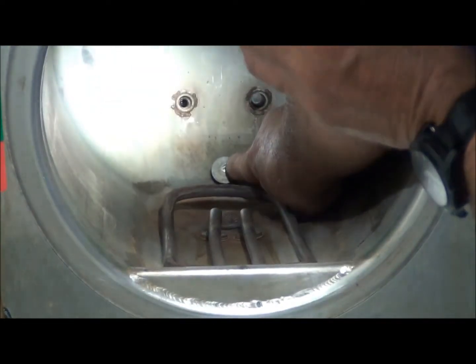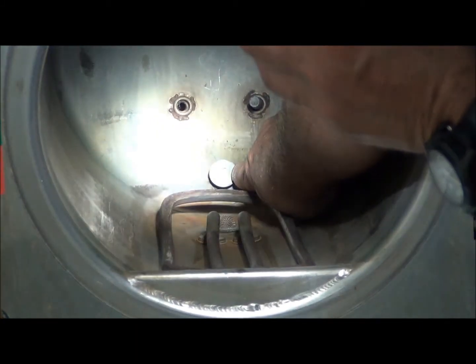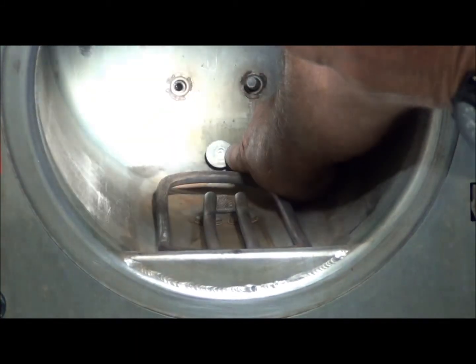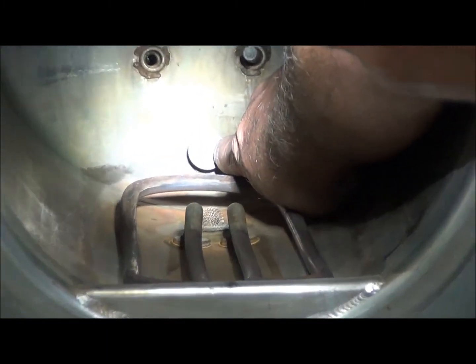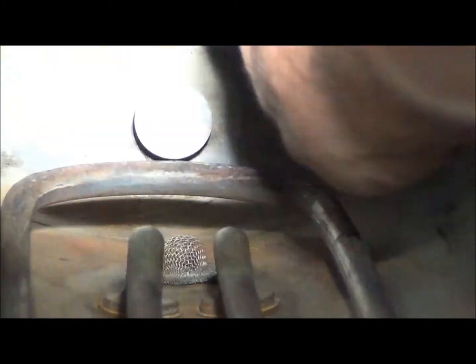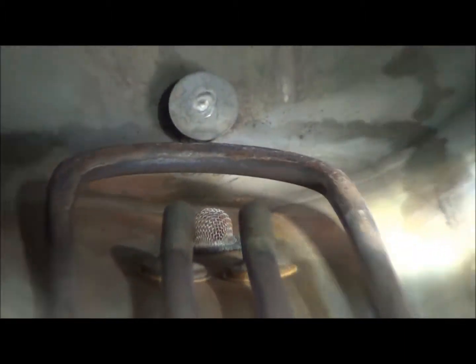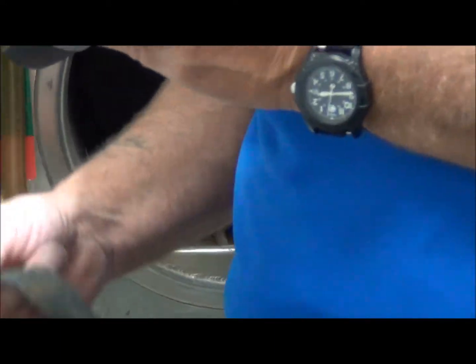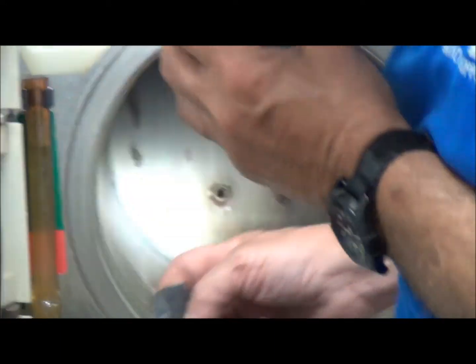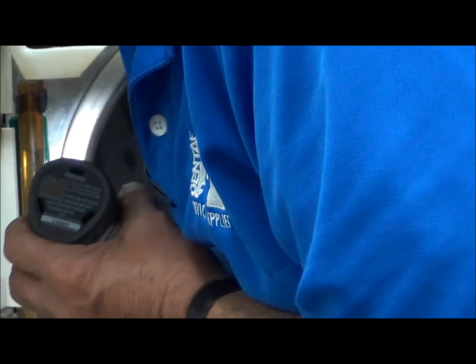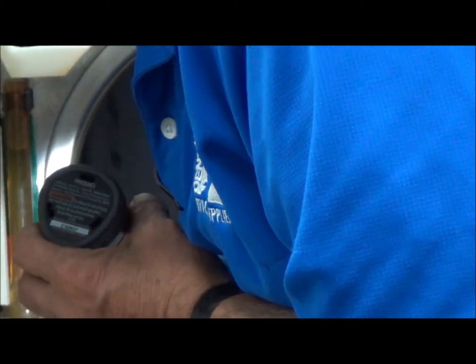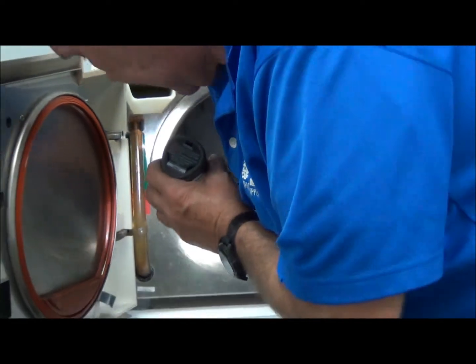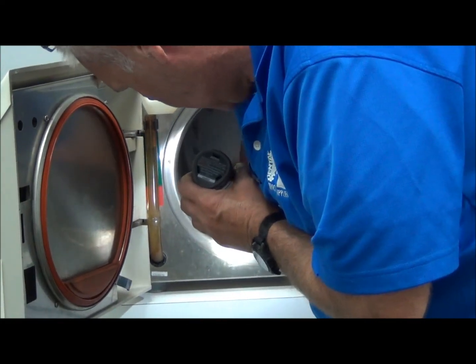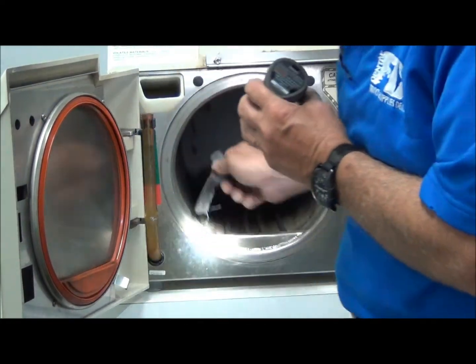At the back of the chamber, we will move to the water level sensor, which is the round disc located at the end of my finger. It looks good and clean. We'll look up about 1 o'clock from there and we'll see a prong sticking out. That is our temperature sensor, ladies and gentlemen. What we'll do is take the same emery cloth that we cleaned the periphery of the chamber with and give this a nice little buffing. Not too hard, just a nice little buffing. This is responsible for every function of the sterilizer, ladies and gentlemen.